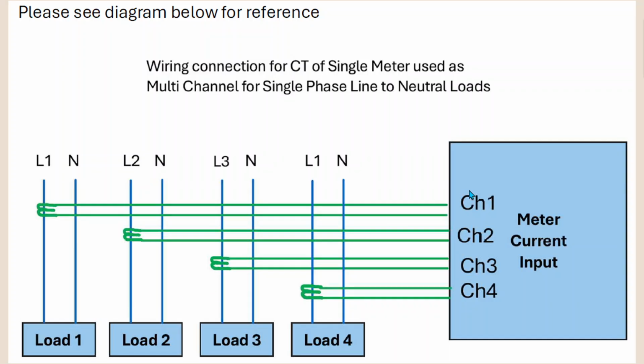As mentioned before, each channel is independently configurable for any phase. It means the first channel can be line 1 neutral, the second channel can be line 3 neutral, or line 1 neutral as well, or any phase for the remaining channels.